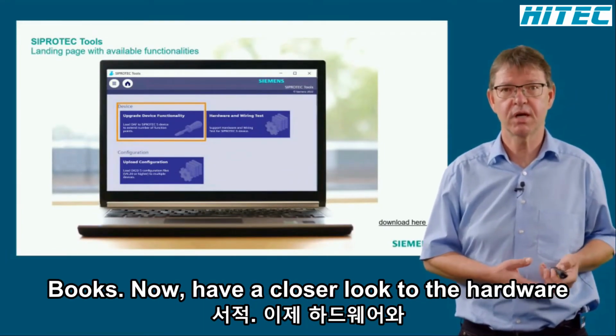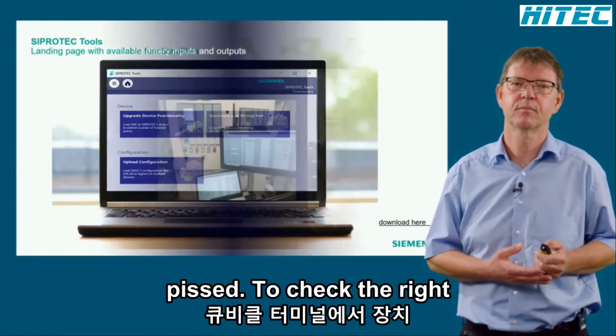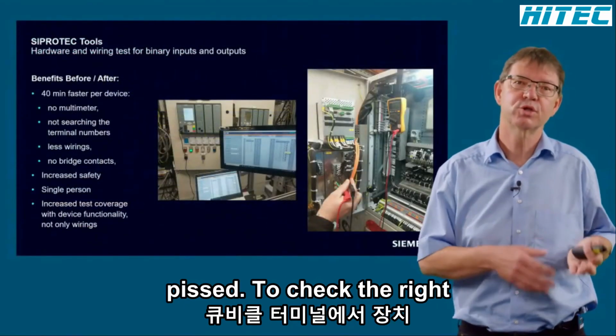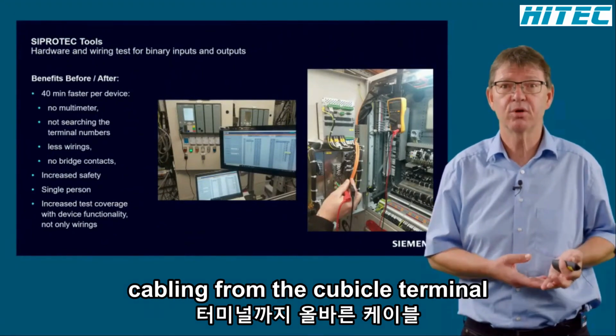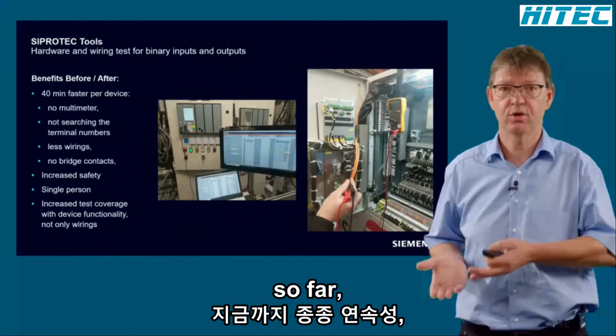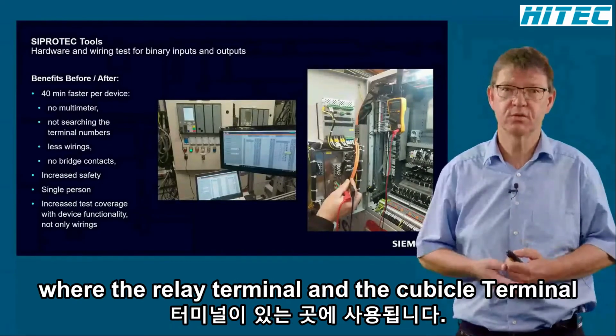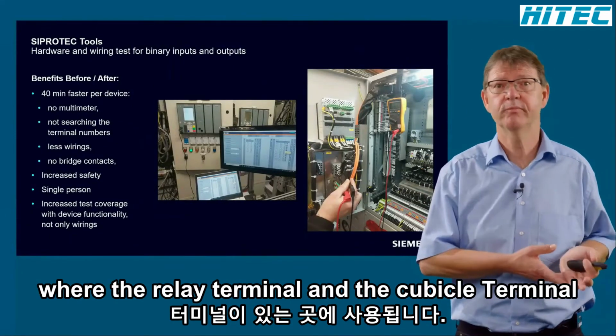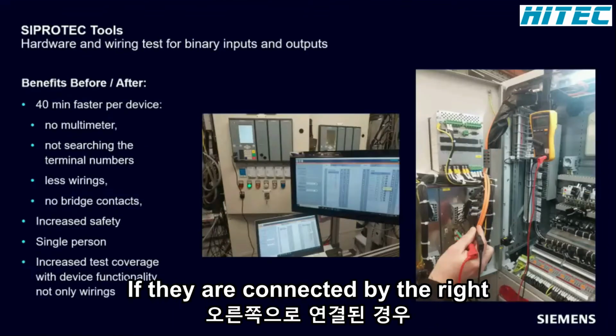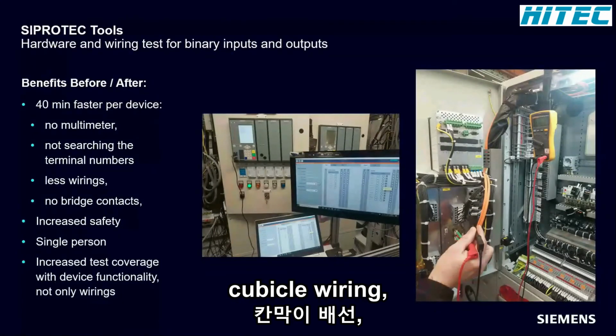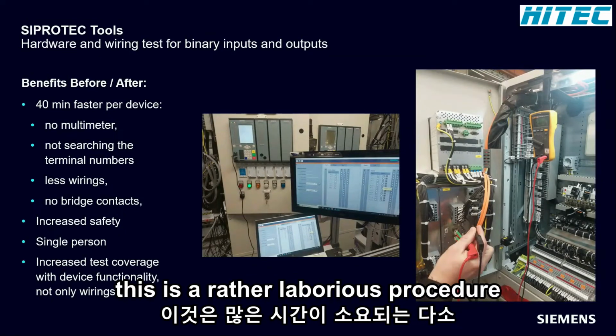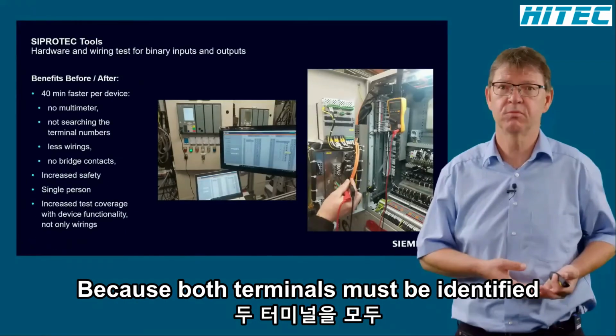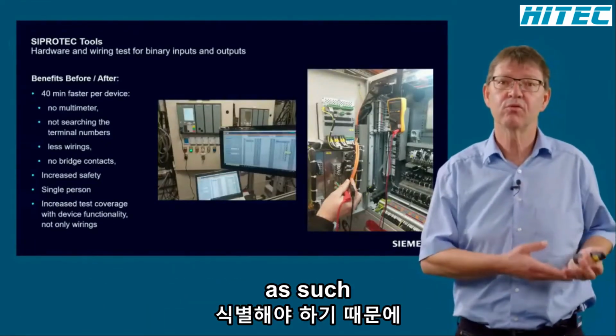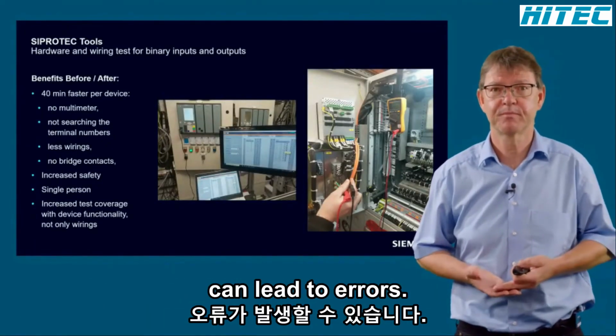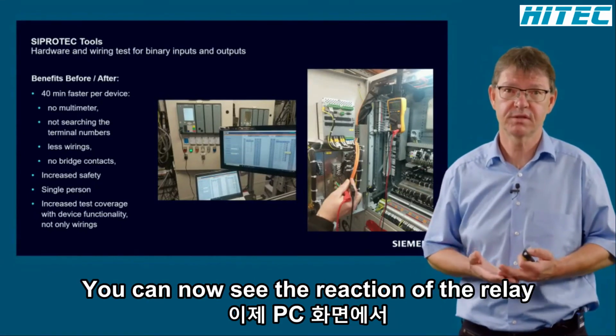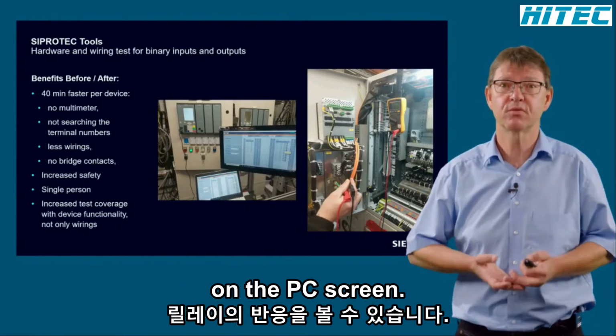Let's now have a closer look at the hardware and wiring test. To check the right cabling from the cubicle terminal to the device terminal, so far often a continuity tester is used, where both the relay terminal and the cubicle terminal are contacted and tested if they are connected via the right cubicle wiring. This is a rather laborious procedure and takes a lot of time because both terminals must be identified. Moreover, this terminal search can lead to errors. With SIPROTEC tools, you can now see the reaction of the relay on the PC screen.